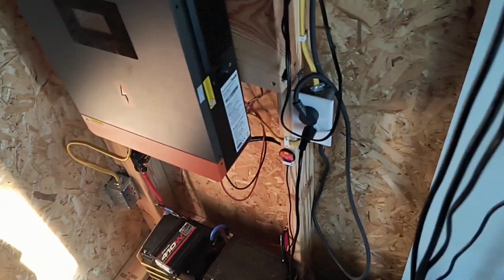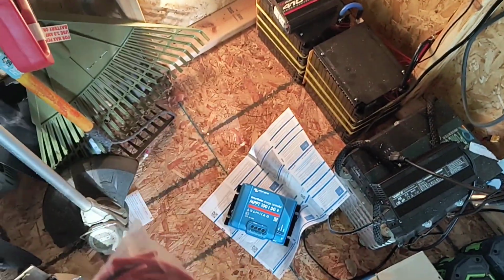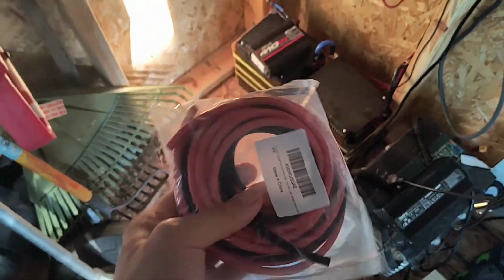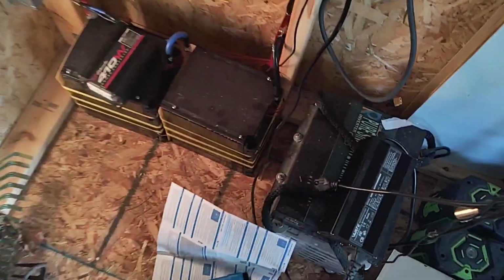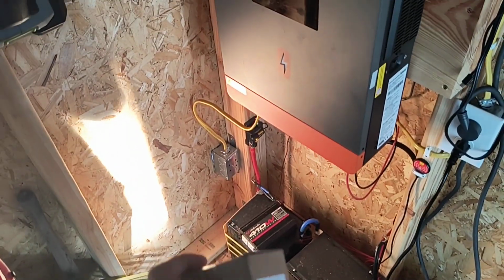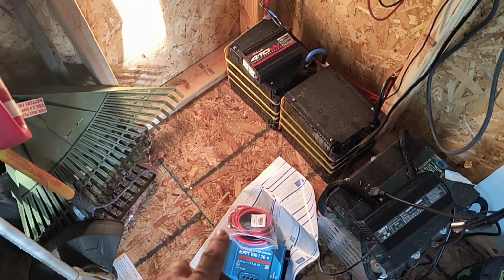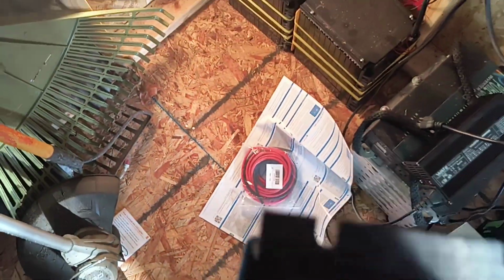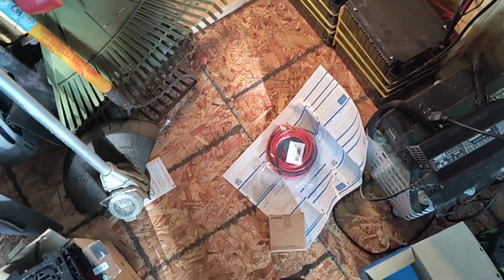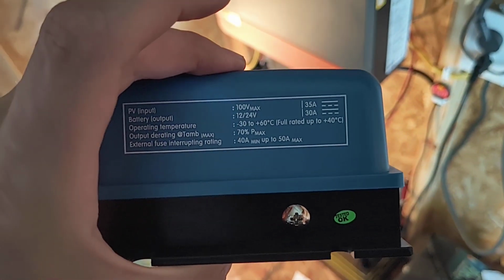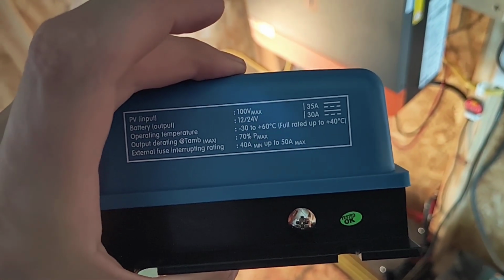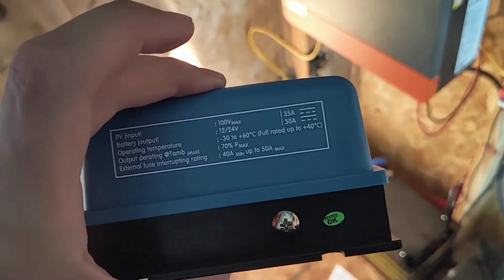I picked up 8 gauge wire that's going to be a little thicker, going from the charge controller to the battery. I also picked up a 40 amp breaker that I'm going to put on the battery side coming from the charge controller, because Victron does recommend a 40 to 50 amp breaker. It says somewhere here on the side: a 40 amp minimum and up to 50 amp max for external fuse.